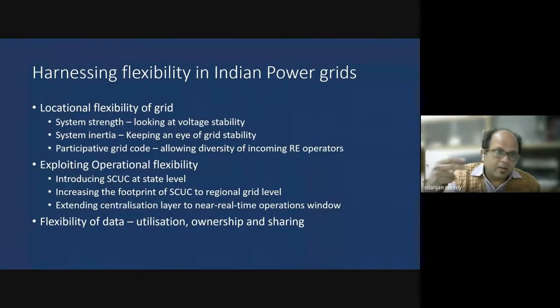So incoming power producers, which are independent power producers, as well as the system operator, they need to collaborate to understand the impact of the incoming technology. And this is only possible if the utility is aware of the incoming technology. That means the incoming power producer should be ready to share details of their technology with the grid operator. And similarly, the grid operator should be ready to share information about the grid with the incoming power producers. Only then can this collaboration help in proper grid flexibility assessment.